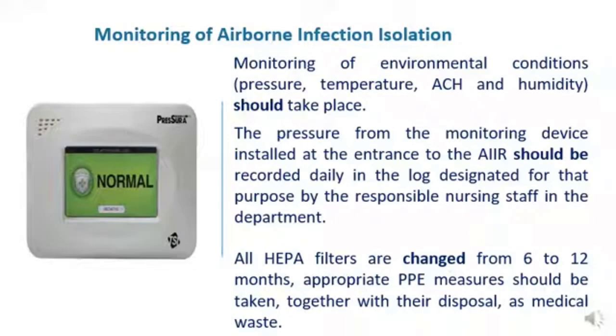From the picture, you can see the type of monitor required — the audiovisual one — for monitoring of the airborne infection isolation room. Monitoring of environmental conditions including pressure, temperature, air changes per hour, and humidity should take place at all times. The pressure from the monitoring device installed at the entrance to the AIIR should be recorded on a daily basis in the designated log by the responsible nursing staff. All HEPA filters are changed every 6 to 12 months, with appropriate PPE required, based on the manufacturer's instructions for the filter, and disposed of as medical waste per infection prevention and control policy and procedure.